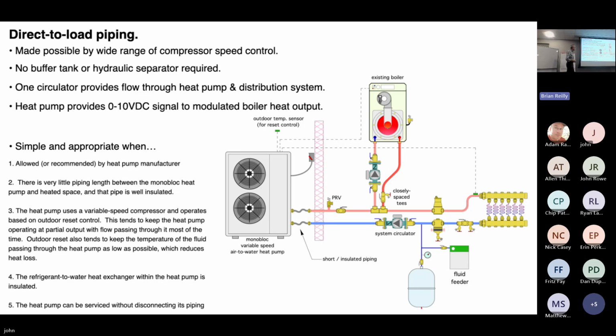And is that PRV there just because we can't have it on the monoblock heat pump? That PRV is there in case that flange gets closed off and the pump gets turned on. Gotcha. And I'm glad you mentioned PRV. It's essential when you have a closed hydronic loop of any sort with a heat source in it that there's a pressure relief valve in that loop. I just had some interaction with a heat pump that literally blew apart inside because the electric elements were on. A valve that was supposed to be open didn't open, and there was no pressure relief valve in the system. And it finally blew apart the lowest rated component, and it just filled the basement up with steam.